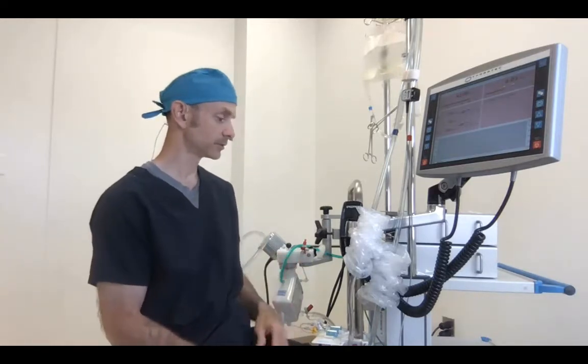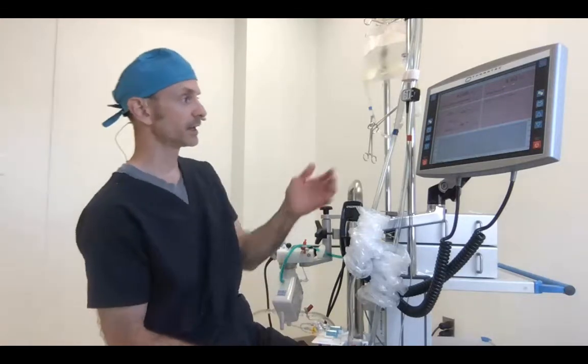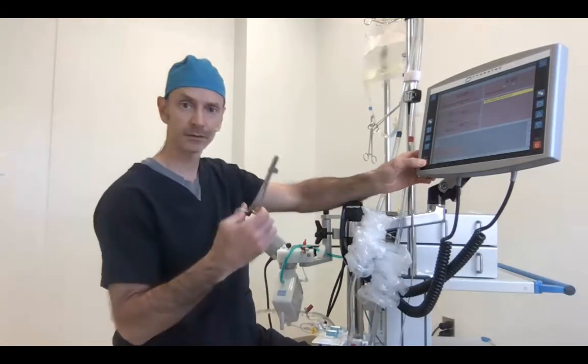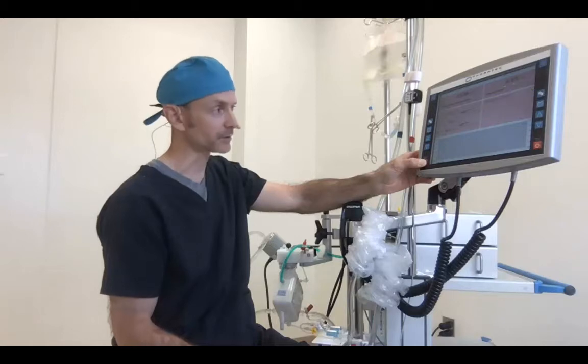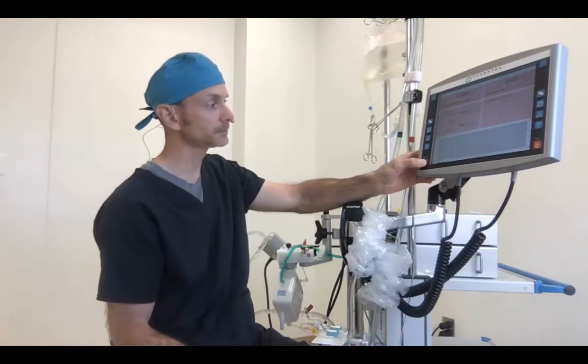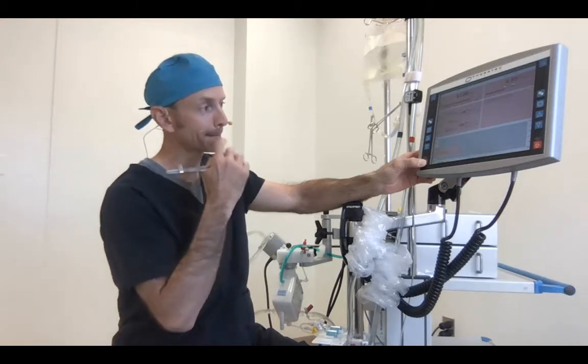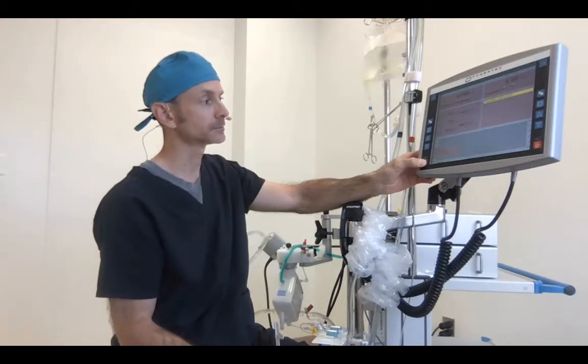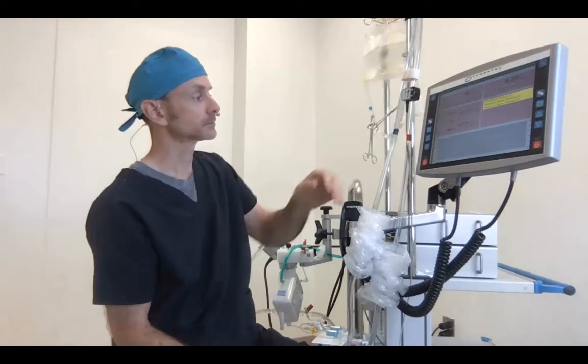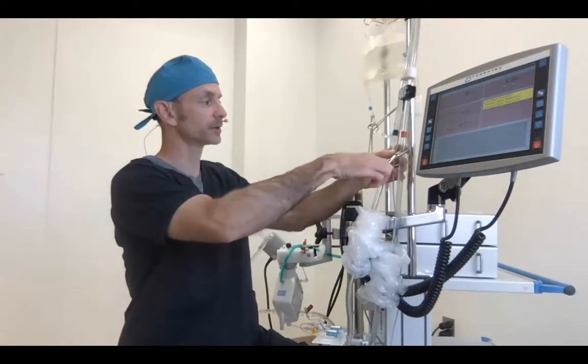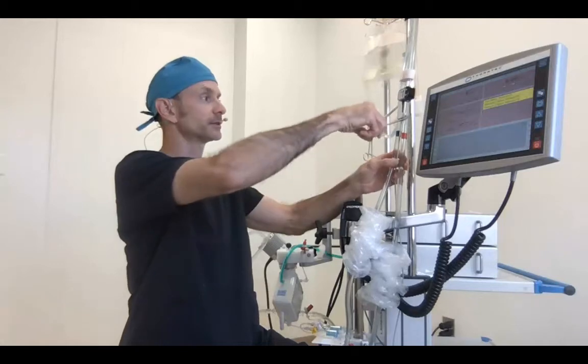So the scenario here is, just say for instance the surgeon just put the cannulas in, and you're initiating flow. You go through all the necessary steps, and that first step, of course, would be to add some RPMs and take the clamp off. So let's stop this pump. Okay, we're going to stop the pump. We're going to put a clamp on the arterial line, as would be good practice. Have a clamp on the arterial line while you're initiating.